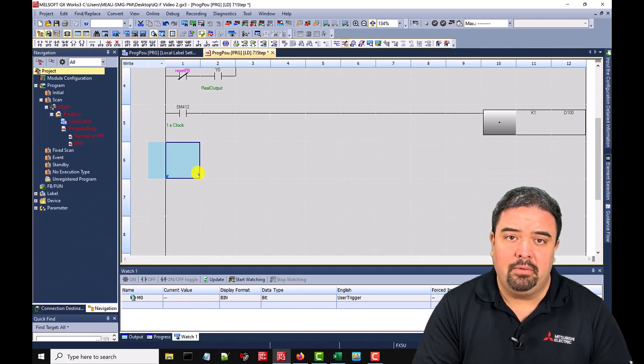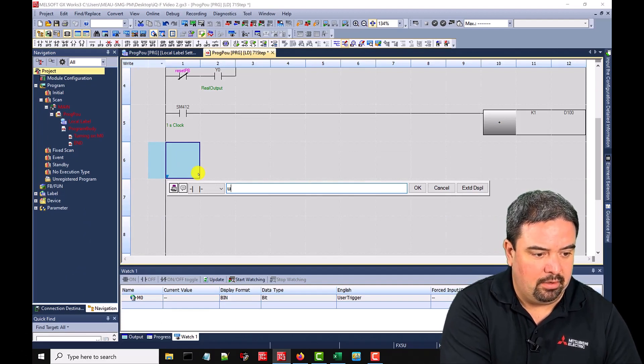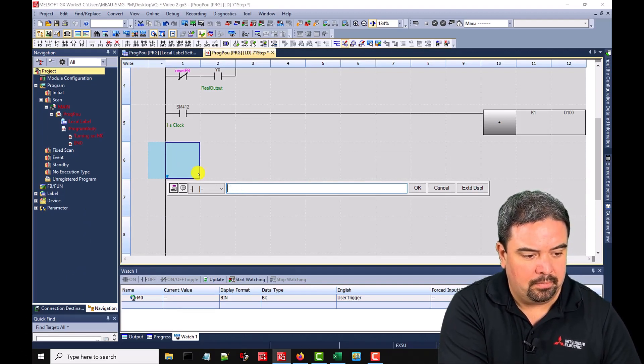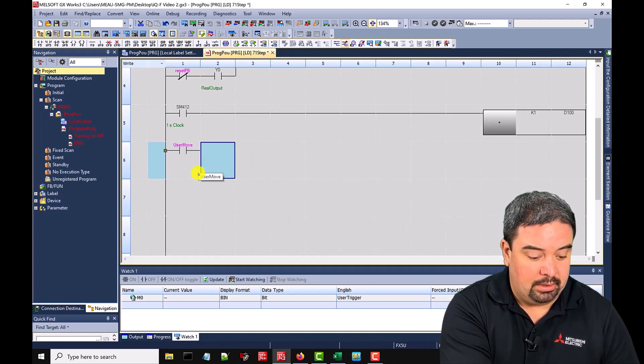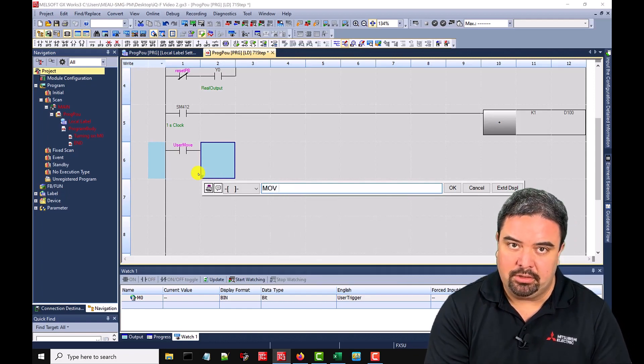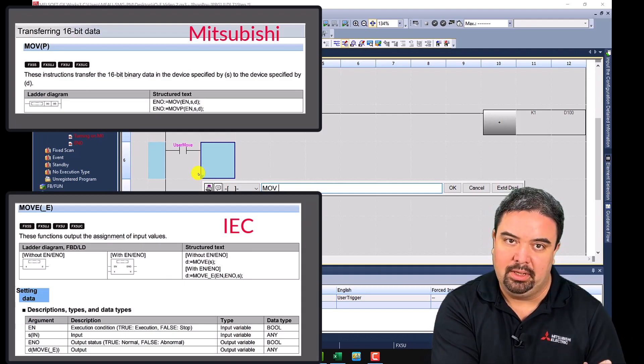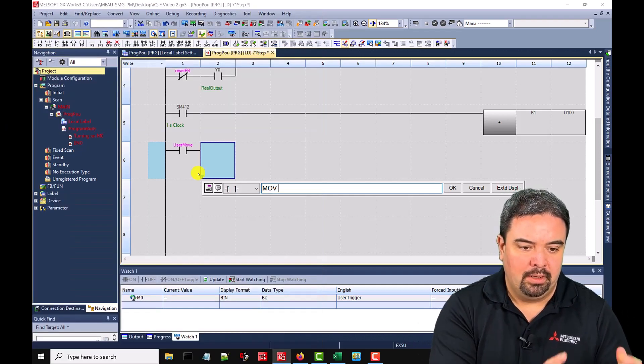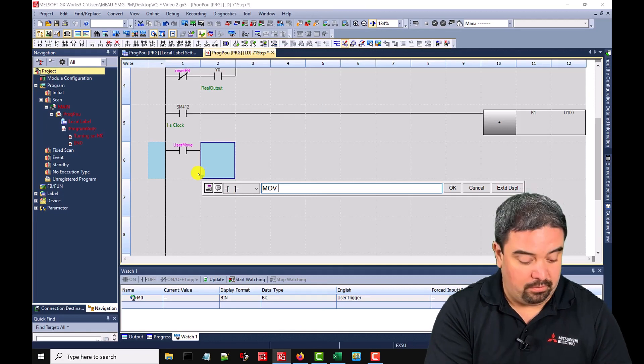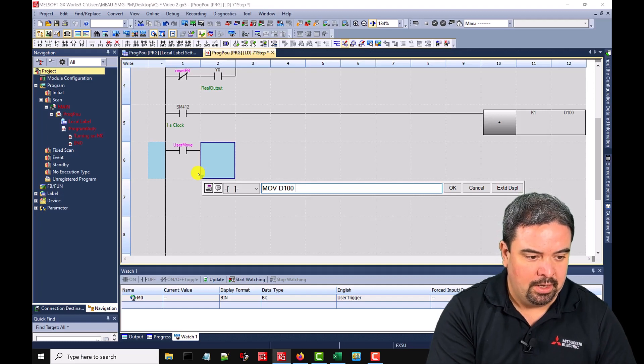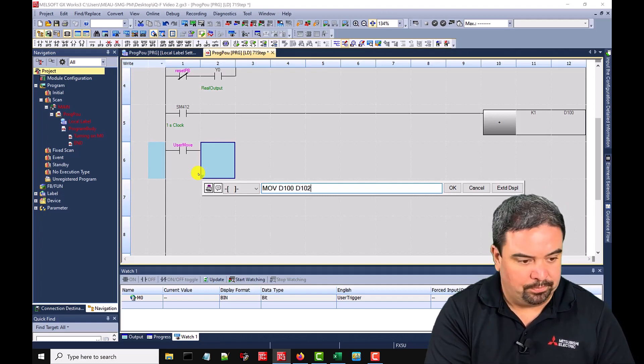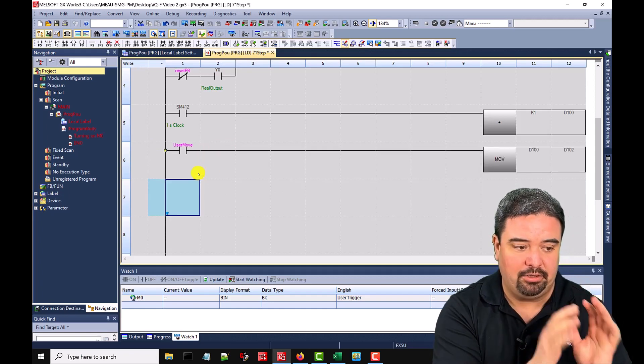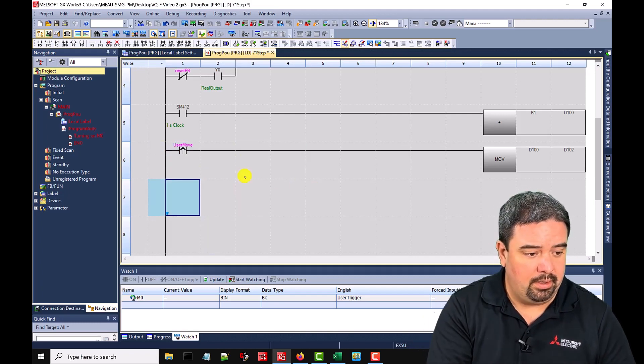Another thing that we might want to do is a move command. So maybe I will give us a user label of move, user move. And hit F8. So I'm going to start out with an MOV and MOV is a Mitsubishi instruction. This is a legacy instruction that will do 16 bit information from one spot to another. So maybe I'll move D100 over to another register. So D100, whatever's populated into that data register, I'll move that into D102, for example, and hit enter. So whatever that, if I trigger this, whatever happens there will be moved over.